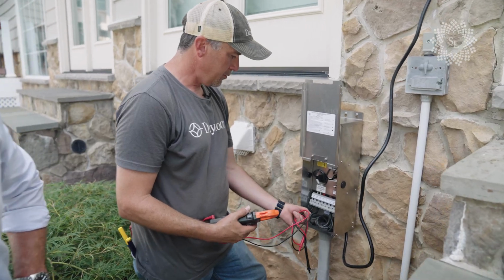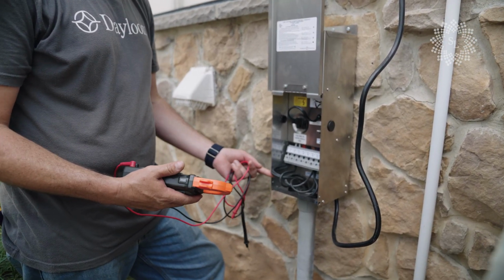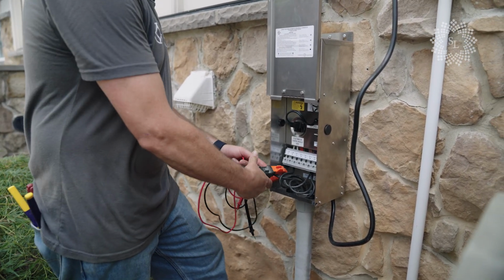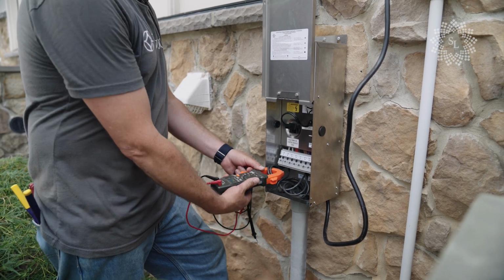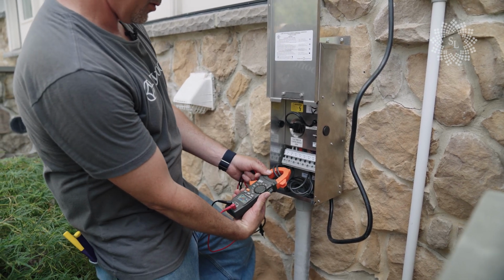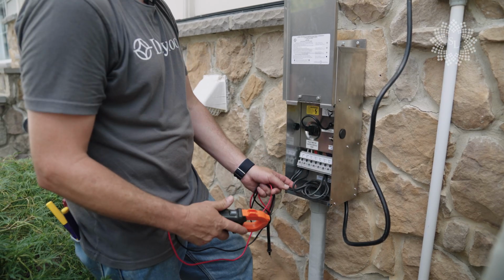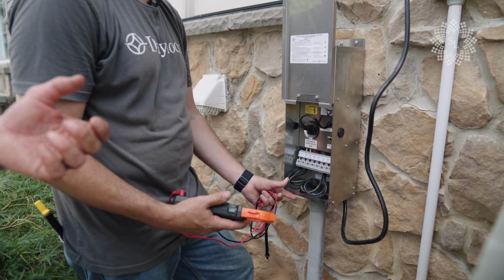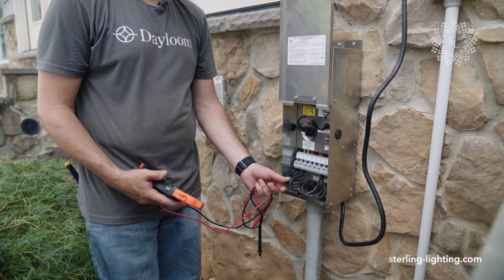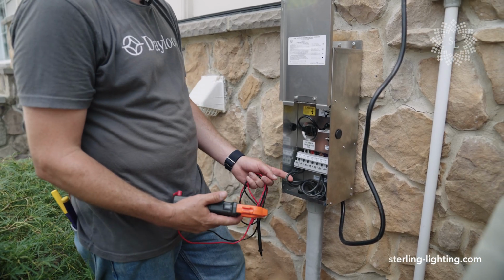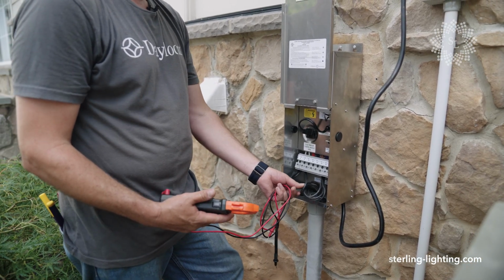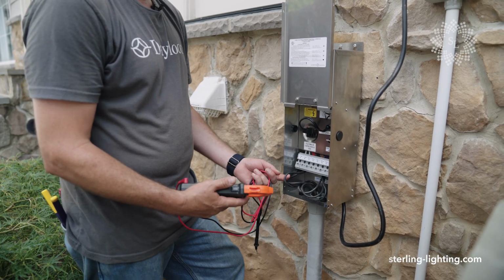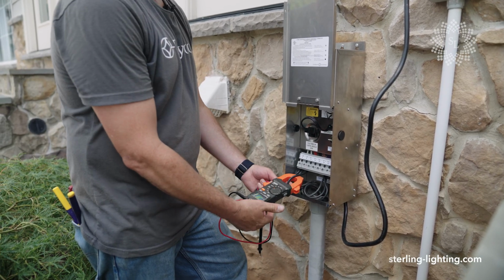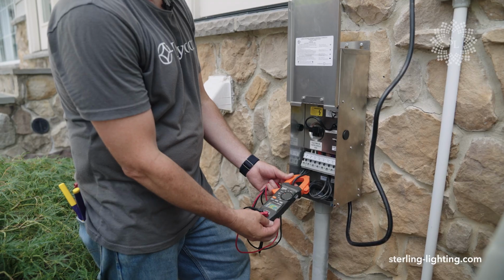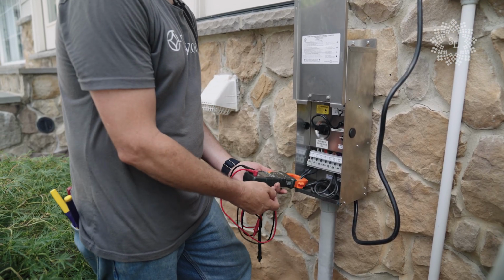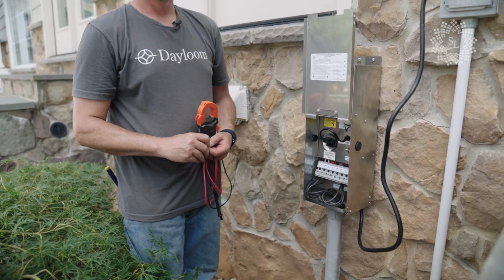Circuit number 1 maxes out at 25 amps, and we are at 10.7, so we are well below there. And you notice he's testing the entire circuit, so he put the clamp around both wires. You could test each one individually or just test one. So this next one is on its own wire, and this one is at 3.9. So these are far from being maxed out.